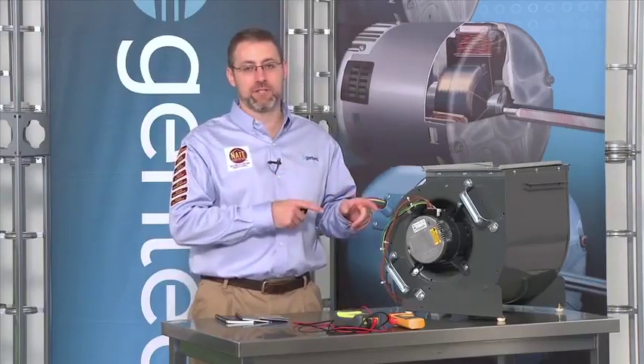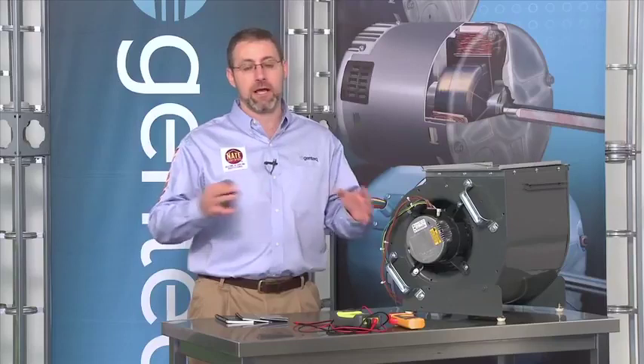Before we get into troubleshooting the X13 motor, we have to remember that the X13 is a motor inside of an HVAC system. So in troubleshooting any system where the motor may not be running or we're having airflow issues, we have to remember that there's a lot more going on than just the motor. The thermostat has to be giving the proper demand to the system. There could be limits or safeties that are tripped, not allowing the motor to come on. And we could simply have airflow problems. That is the reason for our limits tripping or our coils freezing. And obviously the most common airflow problems are registers closed, dirt load in the system, and your filters, your blower wheel, and your coils. So after we've made sure that none of those are the problem, then we can get to actually troubleshooting the X13 motor.